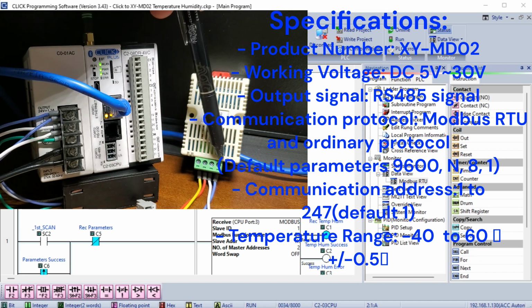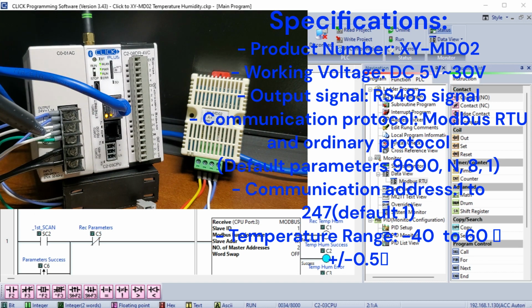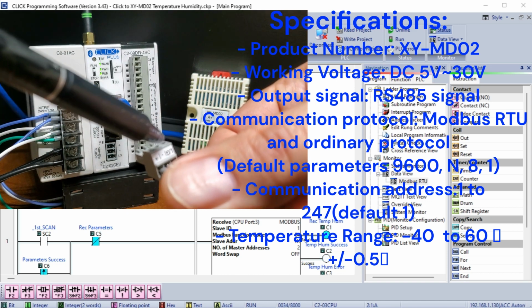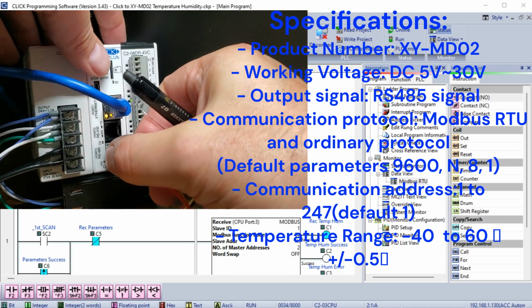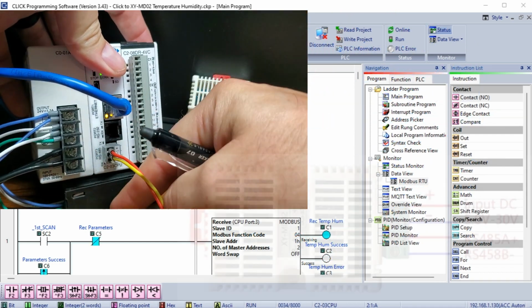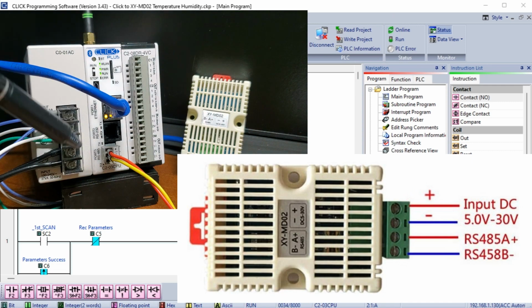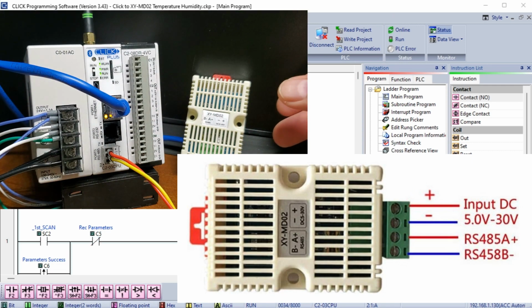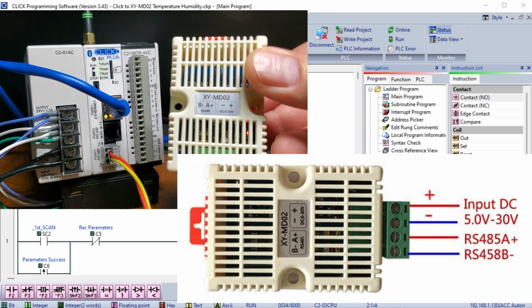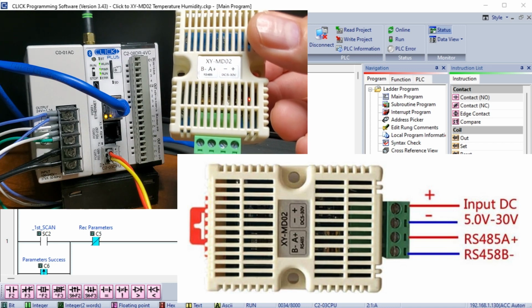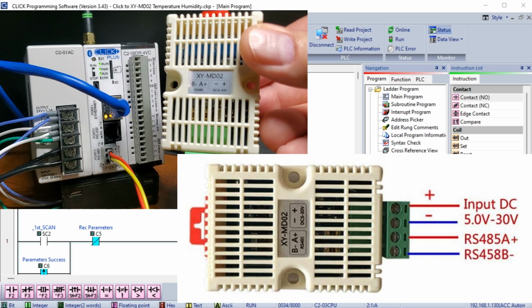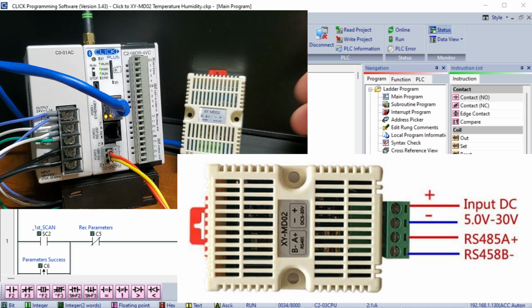The Modbus RTU communication is a 2-wire or twisted pair connection. RS485A+ will be connected to the Click port 3+, and the RS485B will be connected to the Click port 3-. As you can see, the wiring of the sensor is straightforward. We would have to wire the units in parallel to expand this network to several other sensors. Each sensor would have a different unit number assigned so the program client can address the unit.